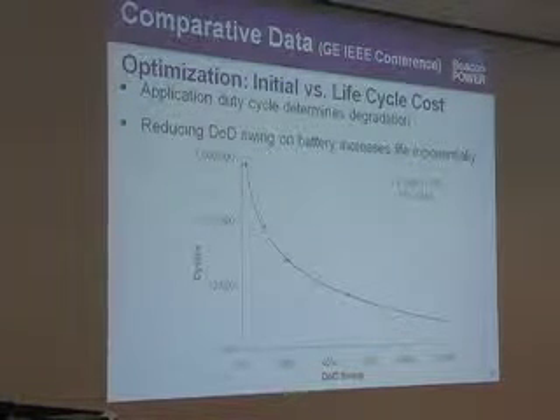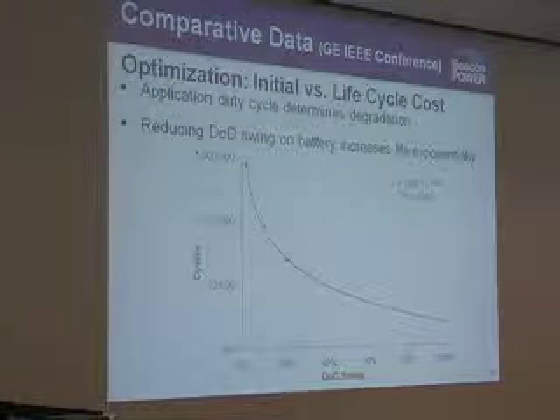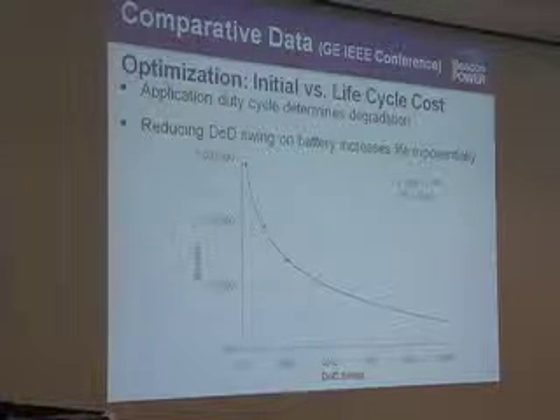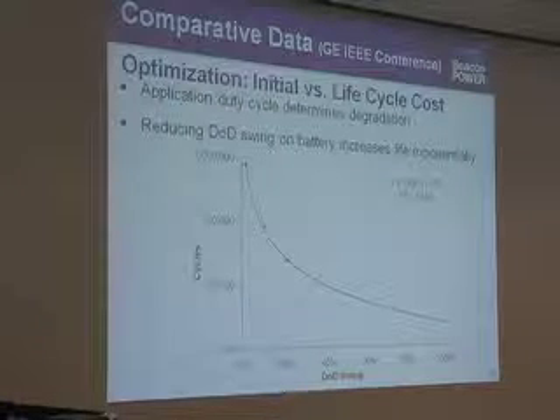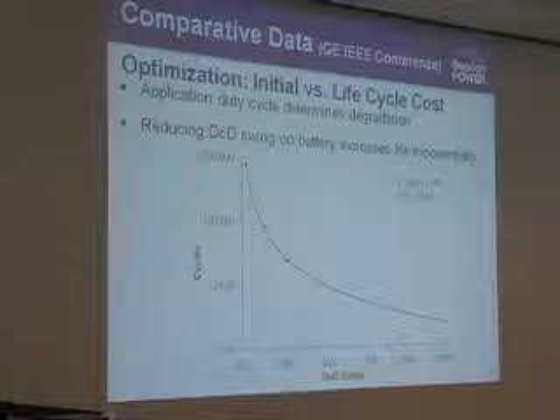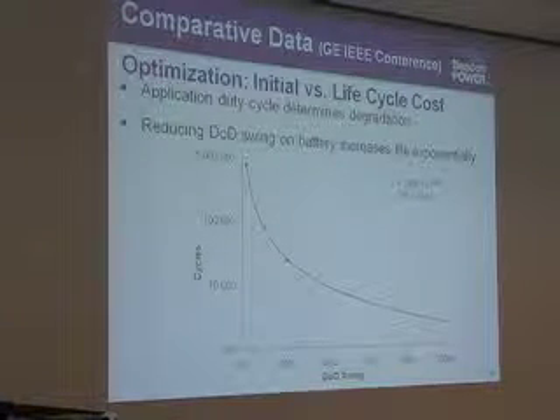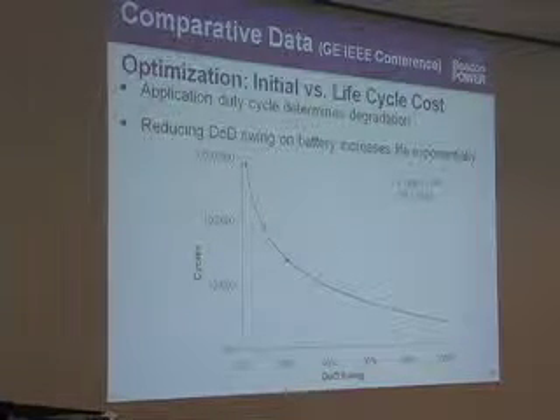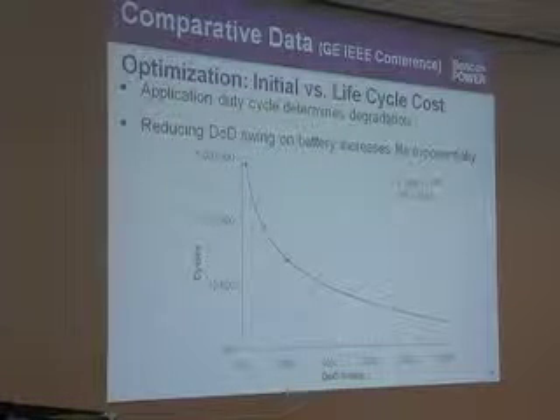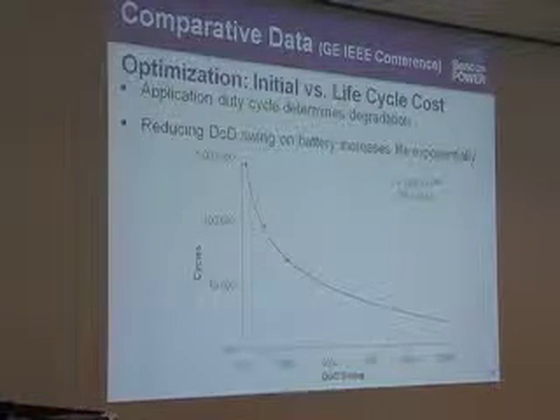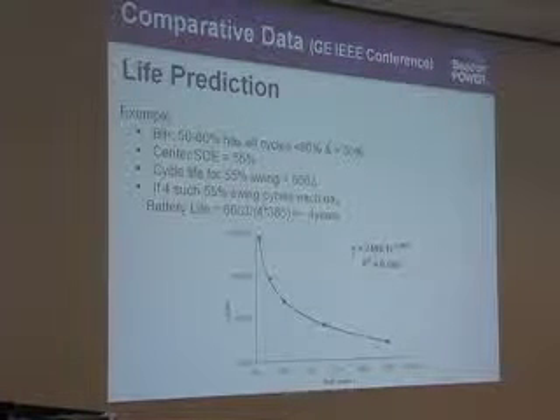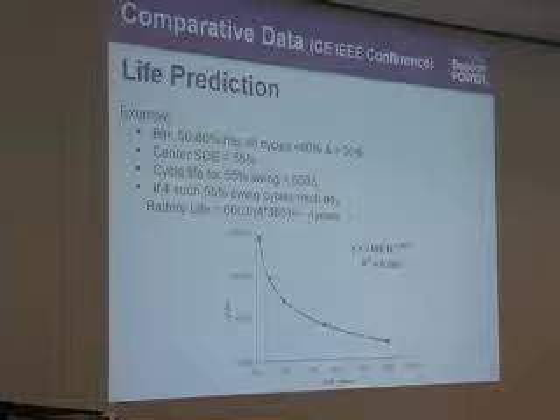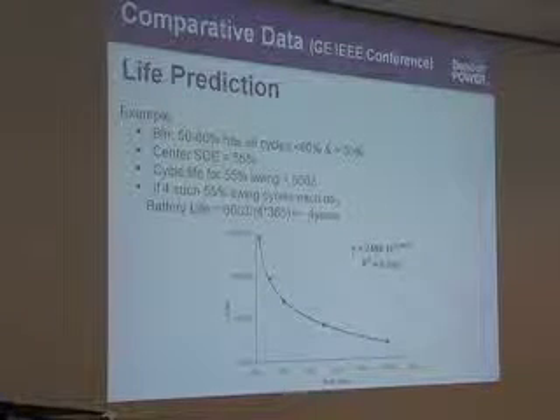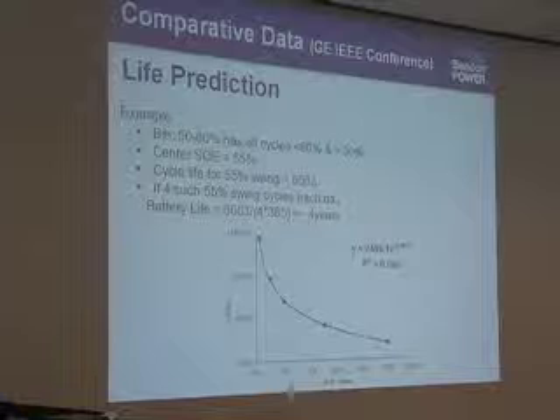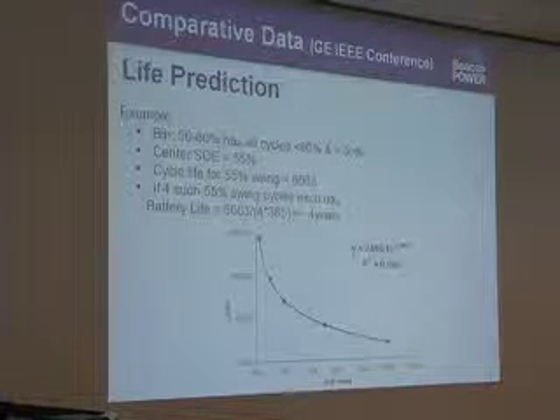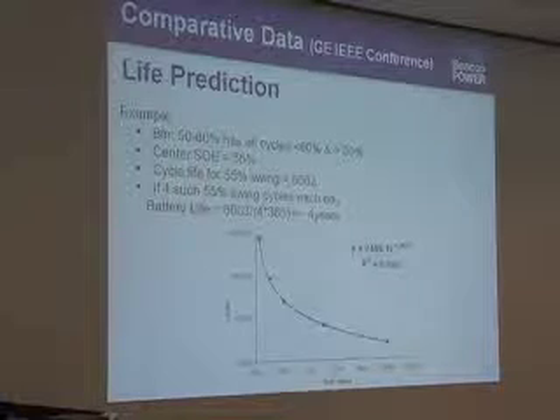This was a graph put together in a presentation from GE at IEEE, and I think this was a lithium-ion battery, where they showed the depth of discharge versus the number of cycles that a battery has. If you're down to that 20%, you can certainly get upwards of 100,000 charge-discharge cycles, but that means your megawatt battery is only a 200 kW battery. Here was a model where they put together that if we did 55% charge-discharge, you get about 6,000 cycles, which would be the equivalent of about 4 years worth of work. So if you're looking at a 20-year asset, then you change the batteries out every 5 years.